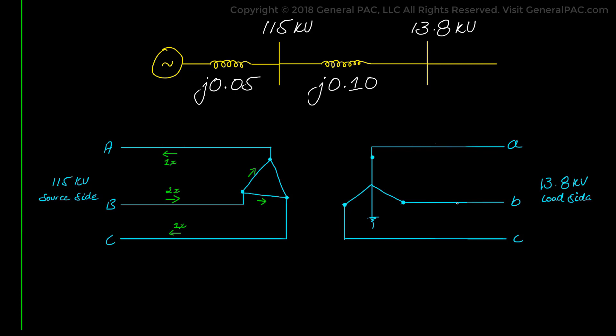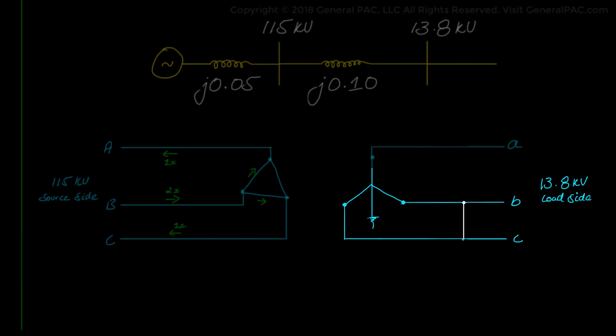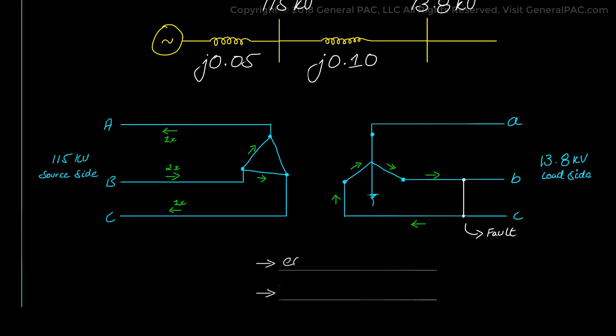We have a line-to-line fault on the 13.8 kV side in which phase B and C are involved. The fault current on phase B flows towards the point of the fault. However, on phase C, the fault current is flowing away from the point of the fault. Therefore, for a phase-to-phase fault, we should expect the fault current on both phases to be equal in magnitude but opposite in direction.